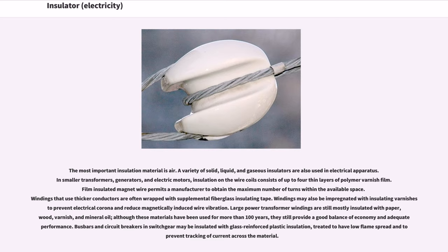Large power transformer windings are still mostly insulated with paper, wood, varnish, and mineral oil. Although these materials have been used for more than 100 years, they still provide a good balance of economy and adequate performance. Bus bars and circuit breakers in switchgear may be insulated with glass-reinforced plastic insulation, treated to have low flame spread and to prevent tracking of current across the material.